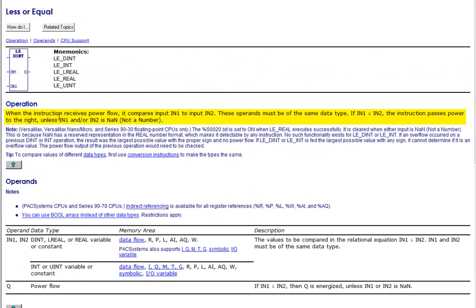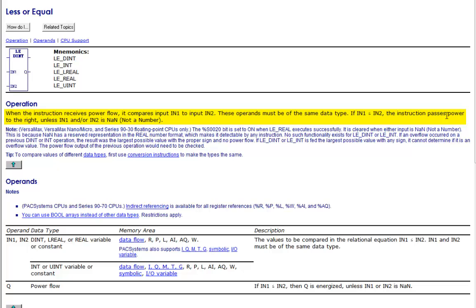The help will come up here and the operation: when the instruction receives power flow, it compares input IN1 to input IN2. These operands must be of the same data type. If IN1 is less than or equal to IN2, the instruction passes power to the right.